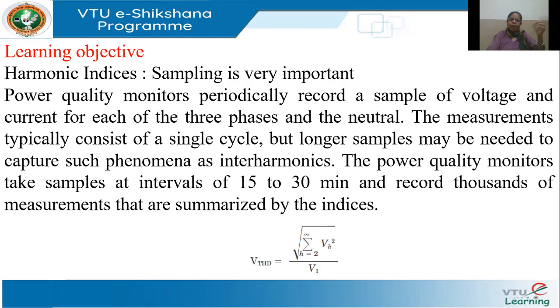One difference you should realize between voltage variations and harmonics is that voltage variations are short. For example, let us say a huge 5000 HP motor is started. It draws a heavy starting current, and momentarily the voltage dips. There is a sag. Once the motor picks up speed, it will recover. The faults which we discussed earlier are all short. Harmonics, on the other hand, are caused by the very nature of the load.